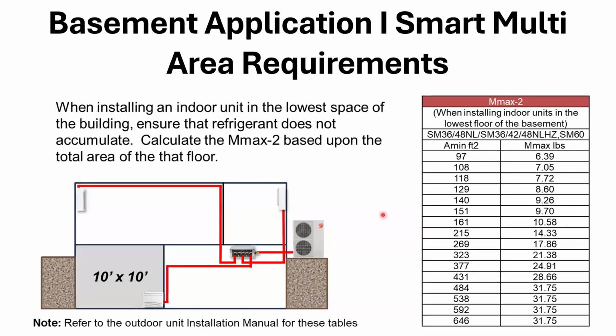So if the max charge is exceeded, then you may need to provide a 1-to-1 system or break the systems up, add some transfer grills, etc. We're going to get into that. There are some options. If this unit has to go in this room, we have to increase the size of this room somehow, so we can put transfer grills and draw air from another room, which allows us to use that square footage in the total. If we can increase that square footage from 100 and get it up to 269 square feet, because we can draw in this basement, this is a bedroom, and we have the living room we can draw from, and we can get up to 269 square feet or 323, then we're allowed 21 pounds of charge in that system. See how that works? So that's what we're trying to do.